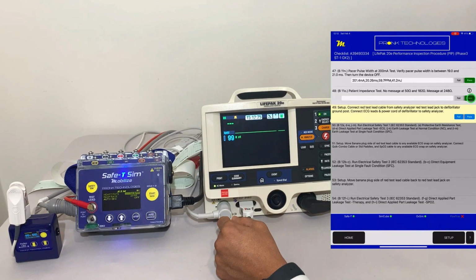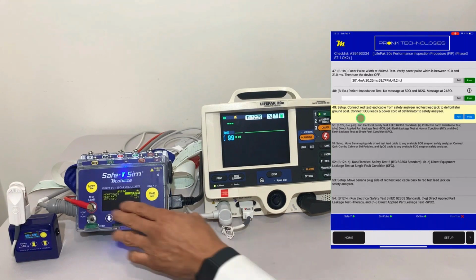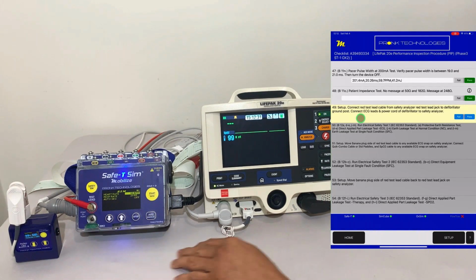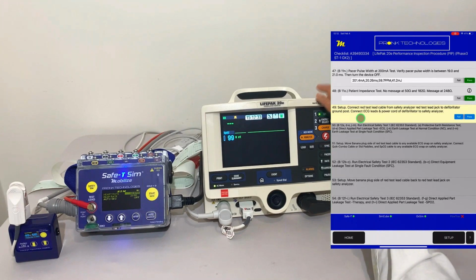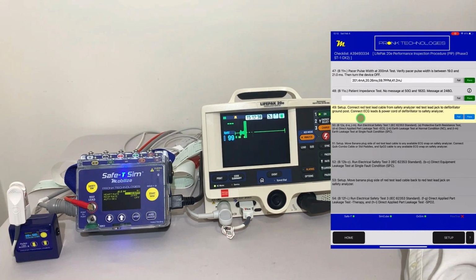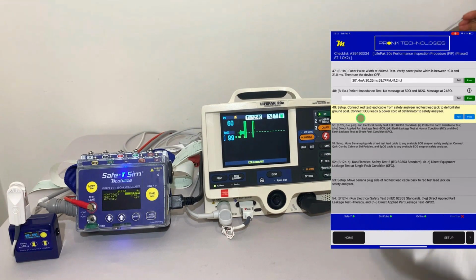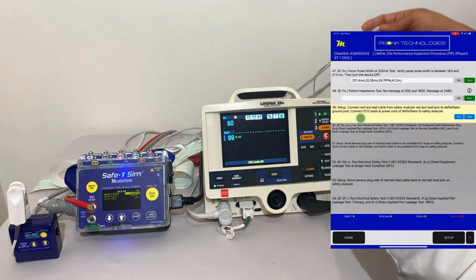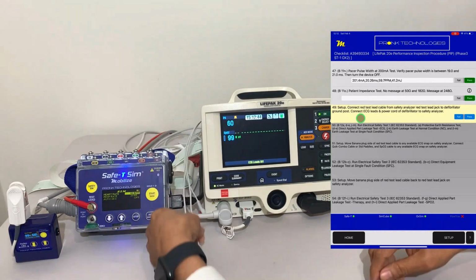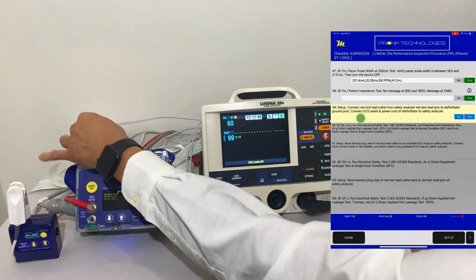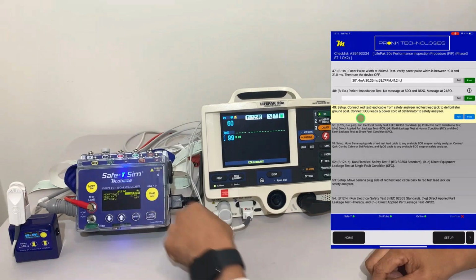So we need to follow the instructions that are laid out in the procedure. In this case, we want to connect the red test lead cable from the safety analyzer to the defibrillator ground post, which we've done. Now we need to move the ECG cabling from the defibrillator analyzer over to our safety analyzer. So let's go ahead and connect that up because we're going to do a leads leakage test here.